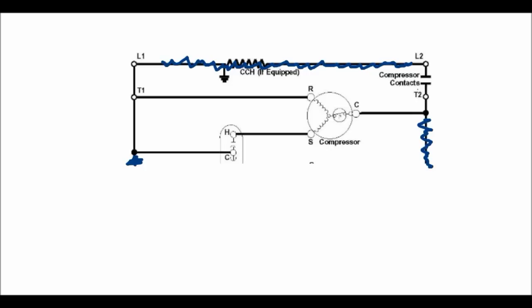So this is how you're going to want to look at your schematic diagram, ignoring everything else around it. And as you can see here, there's only a couple of components you're going to need to check. The compressor contactor, the compressor itself, and the dual capacitor. That's it. One, two, three components that you're going to have to check.